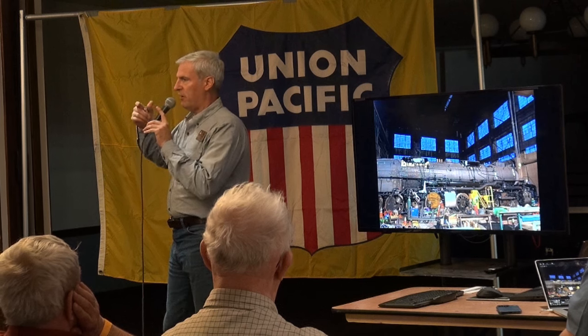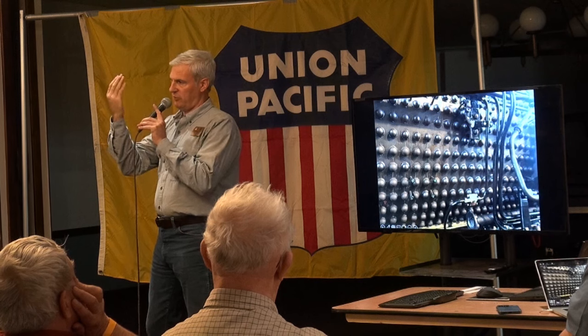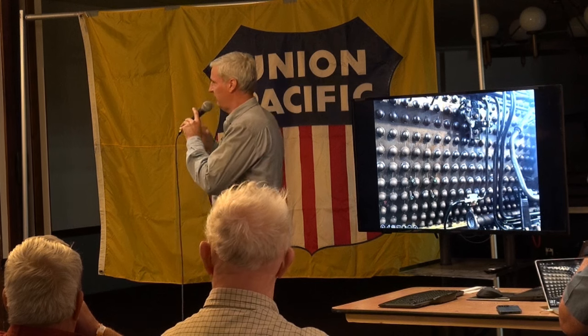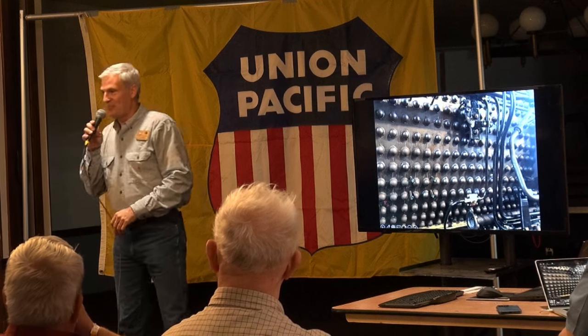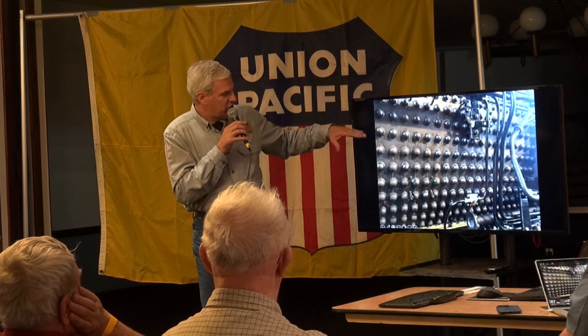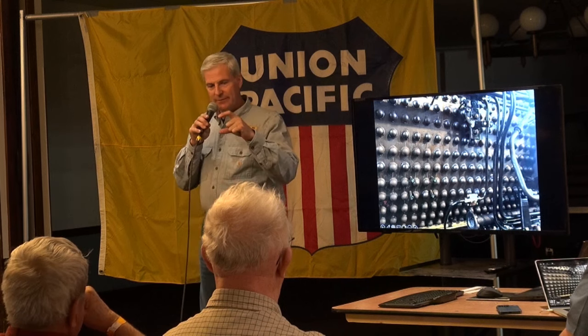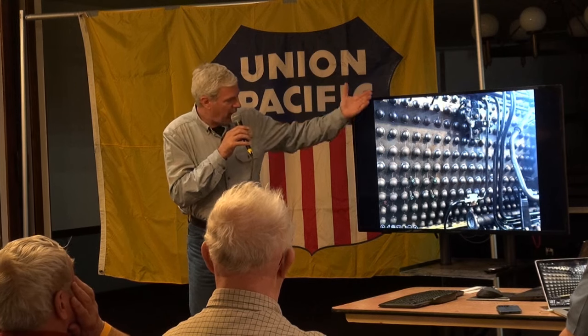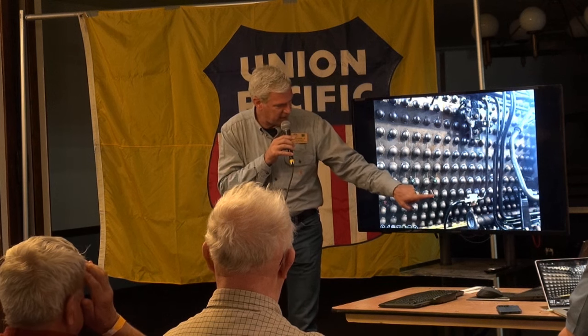And the stay bolt itself is threaded from one side to the other, and it secures that heat transfer surface. There's a lot of different varieties. I actually have around the corner a cart, I usually bring a whole little cart of rusted stuff. And when we're done here, I'll get a few of those out and I'll show you what those are. These are the actual caps. So on the boiler, this plate is an inch and a half thick and thicker in some cases. And all of the stay bolts are inside each one of these little caps that make it steam tight.